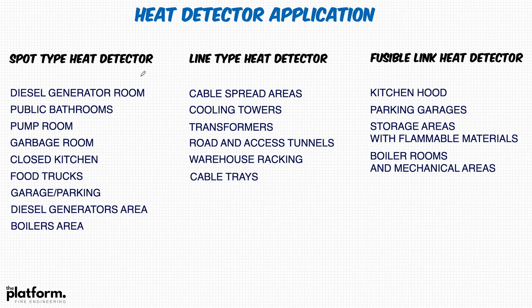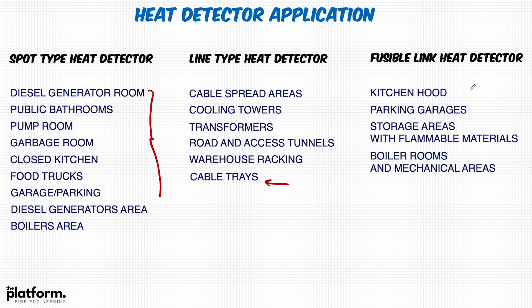The applications of each heat detector type are as follows: the spot type is suitable for the previously mentioned rooms. The line type heat detector is suitable for cable spread areas, cooling towers, transformers, road and access tunnels where spot detectors cannot be installed, and warehouse racking, cable trays, and underground areas. The fusible link heat detector can be installed in kitchen hoods — as in fire suppression kitchen hood systems.